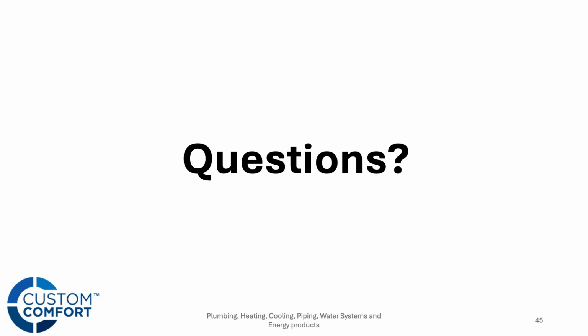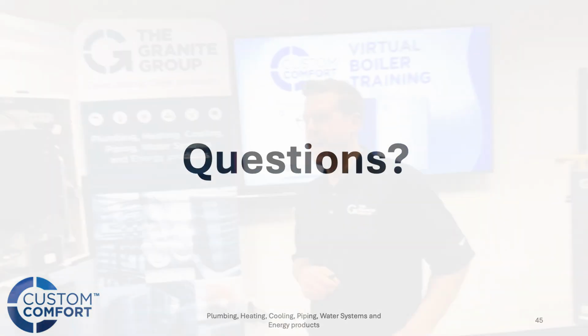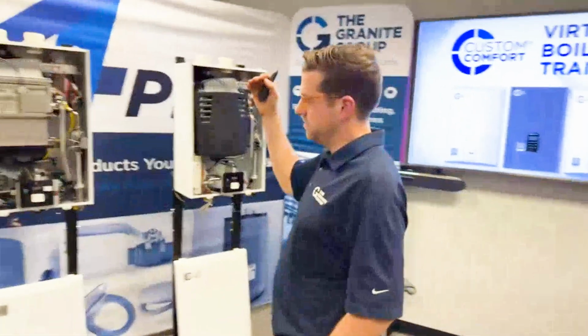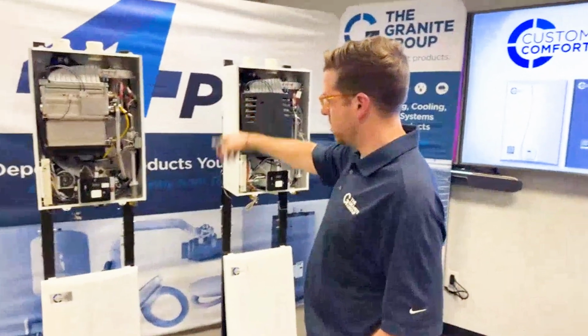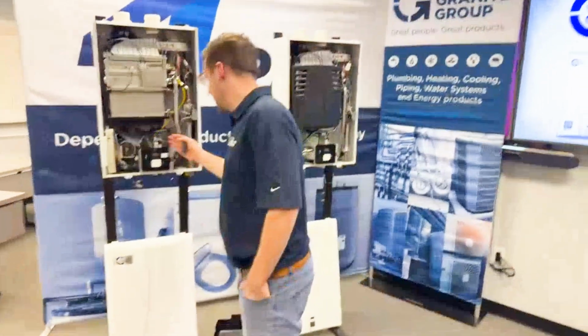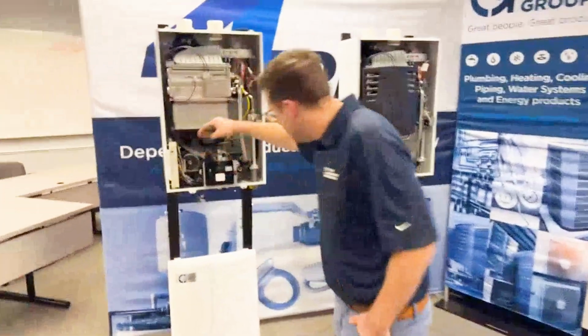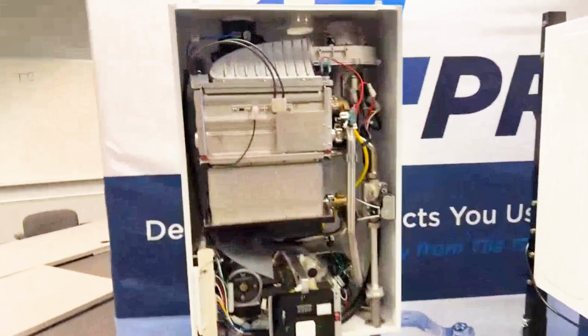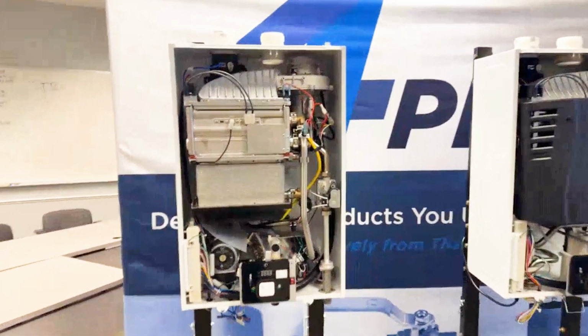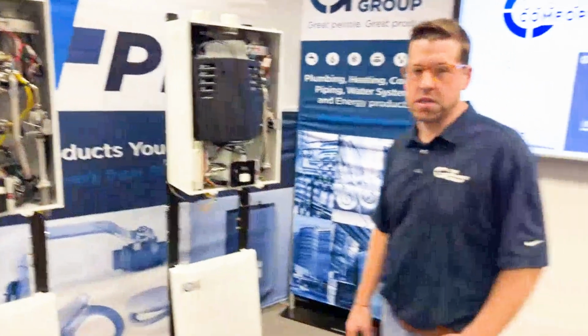Yes. All right, another one. Ginny asked, is there any sort of air purge on the boiler? Or is it a purge through the piping? There is air elimination inside the boilers. Your best bet is going to be to purge through the piping. So again, the question was, internal air elimination on these in terms of purging and getting them set up. There is an air vent in the back here, but your best bet is really going to be purging through the piping of the system, right? That's going to be your best bet for purging these on setup.